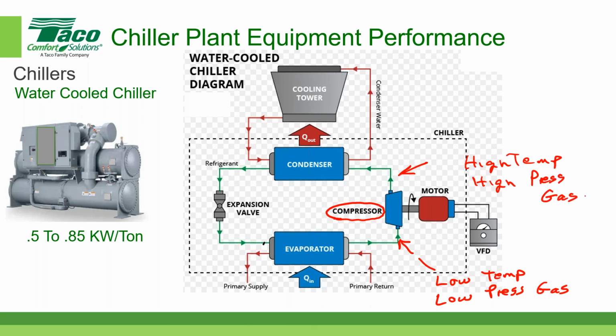And one of the things that manufacturers try their best to do is make sure that the refrigerant enters the compressor as a gas and leaves the compressor as also a gas. That's important because if liquid gets into the compressor, it could really, really harm the compressor.